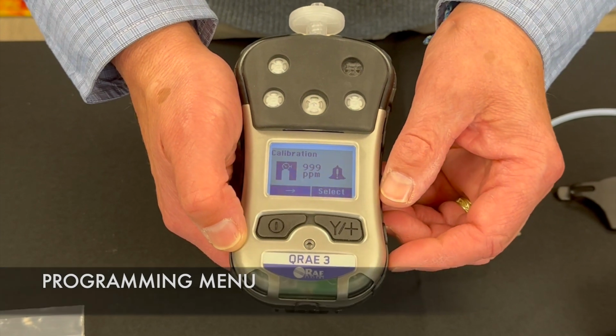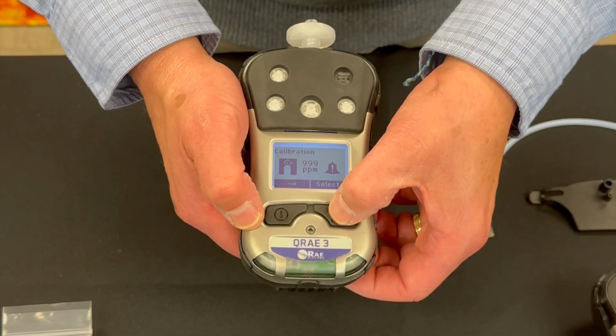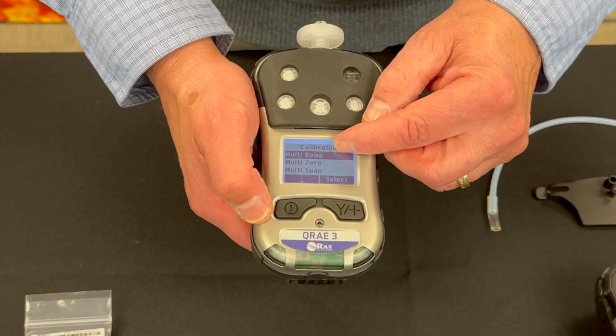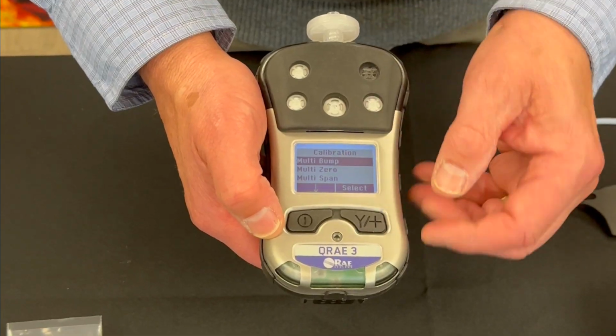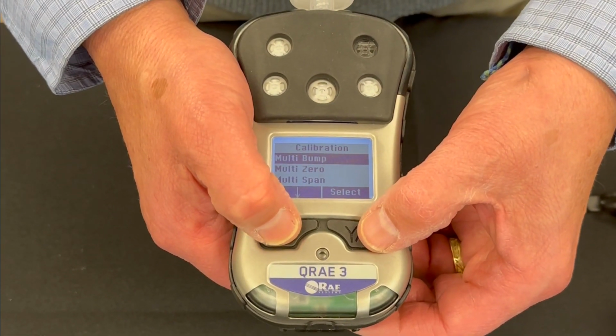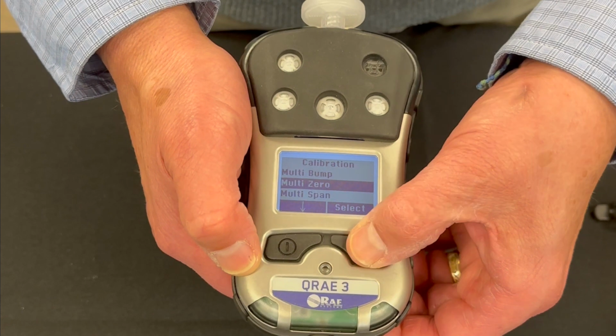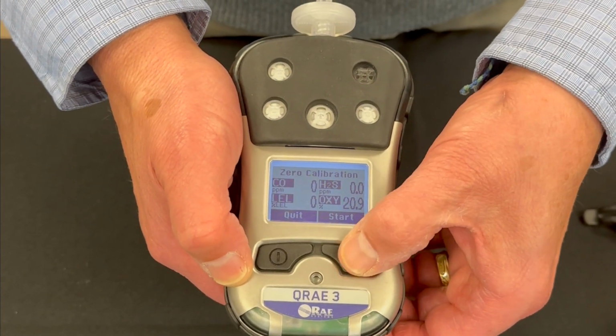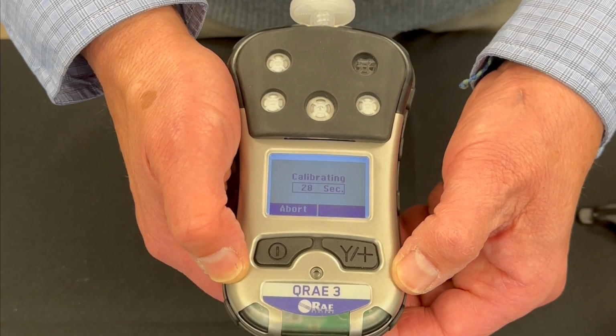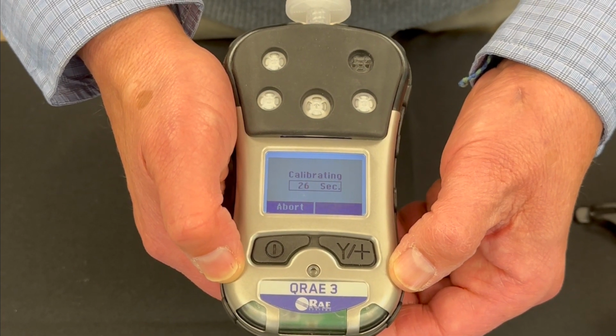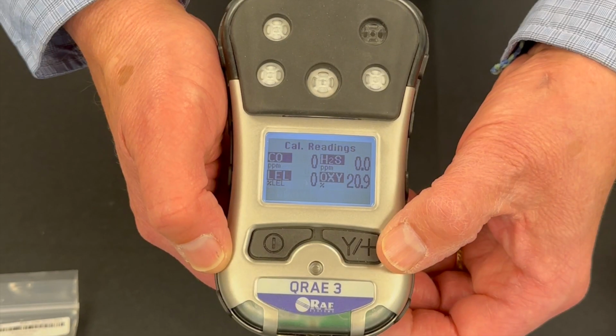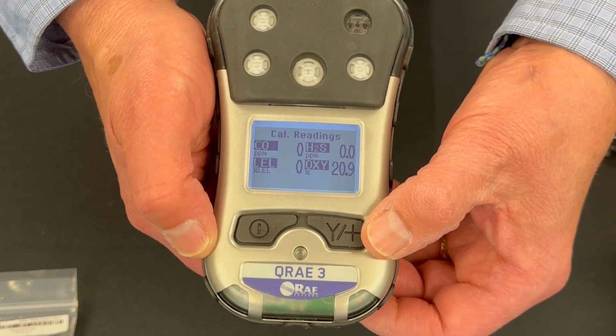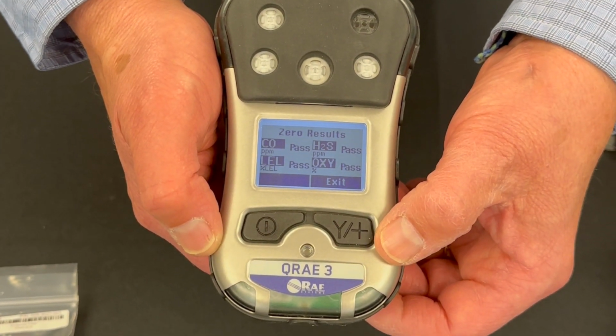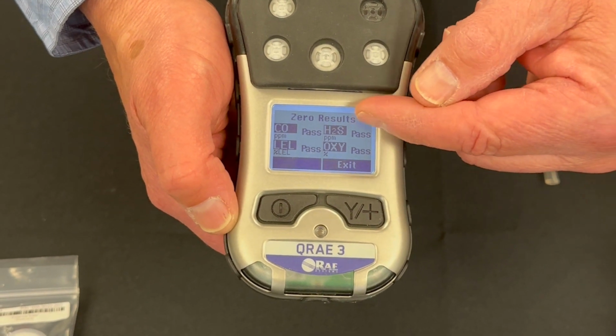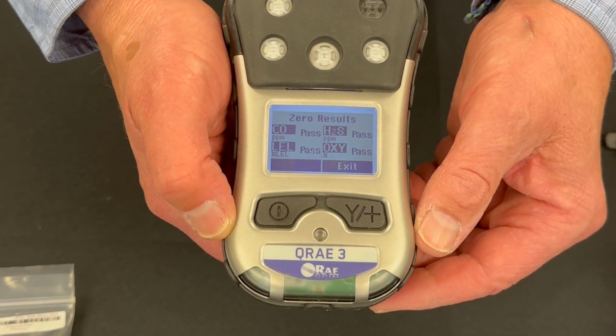I find my calibration icon. I hit Select. First, it's asking me for a multi-bump, a multi-zero. I'm going to bring the menu down into multi-zero, make my selection, start that. It's going to go through its 30-second fresh air setup. So we've completed our fresh air setup. Takes about 30 seconds. I have pass, pass, pass, and pass for all my sensors.